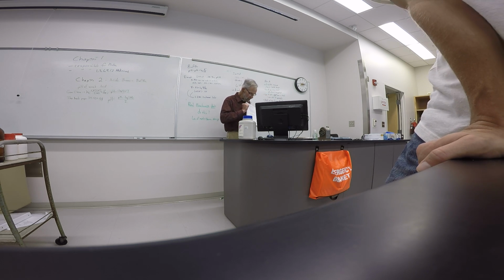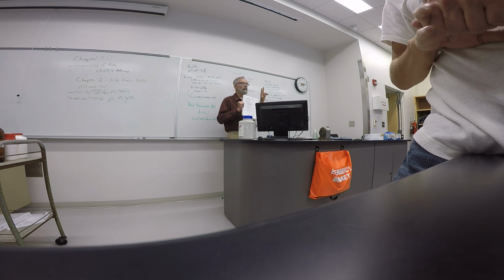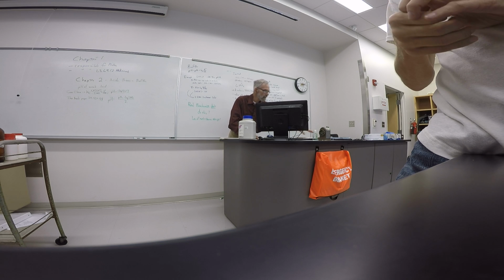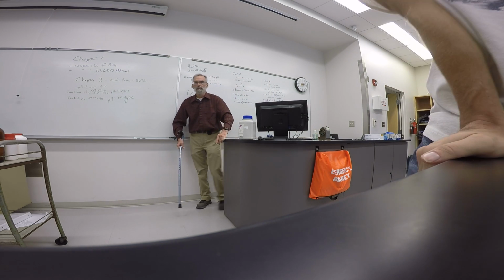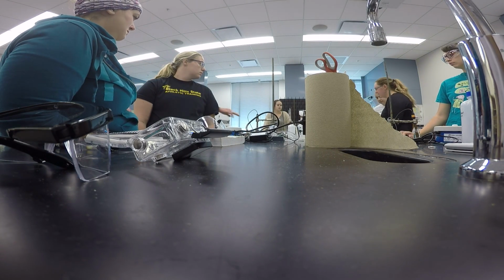Now, one thing it mentions in here that I'll emphasize, when you calibrate the pH probe, you should choose 2 pHs to calibrate it. The way the bench is set up, on each side of the bench, I have a set of 3 different calibration buffers, 4, 7, and 10.